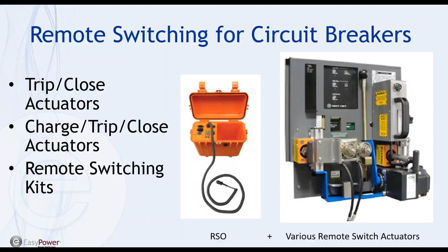We do have to have different switch actuators for different breakers simply because the geometry is different on every breaker, and things like torque are different on different breakers too, so we do have to design solutions for every breaker out there. The good news is CBS ArcSafe really does have a solution for just about every type of breaker in North America, dating all the way back to the 1960s, maybe earlier.